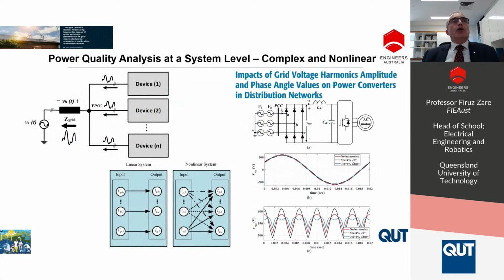And we have also done lots of analysis for grid-connected inverters. We are aware of the complex and nonlinear behavior of the inverters at the system level. When these effects are happening, the background voltage harmonics can affect the current quality, and we have realized that this can increase or decrease the current harmonics from each device. We have published several papers to demonstrate the nonlinearity of the system.